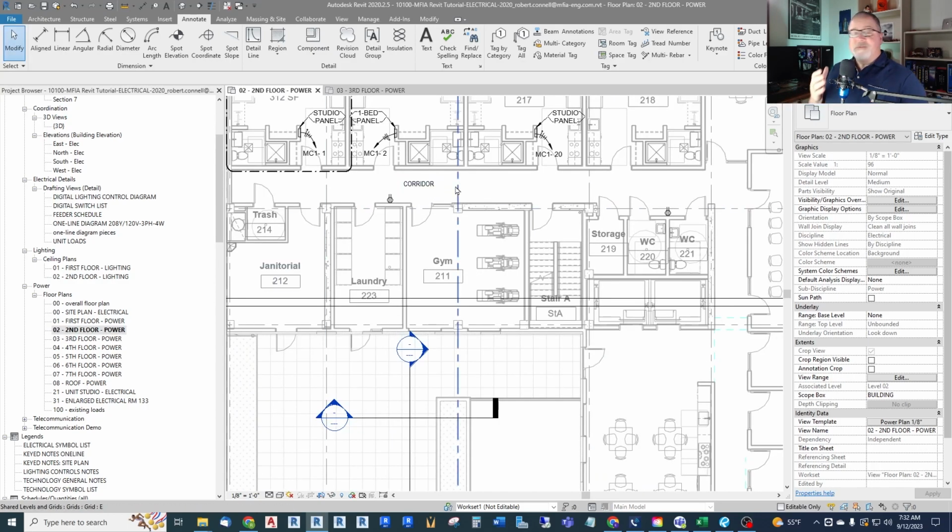And so sometimes a design decision comes down to whether we circuit these horizontally, so from here to here, 50 feet away, or do we circuit them vertically floor to floor? And of course, the argument is cost. If we go floor to floor, we only have a short run of circuiting conduit and conductor, versus going horizontally with more than 50 feet to get between them. So often we will circuit these vertically.